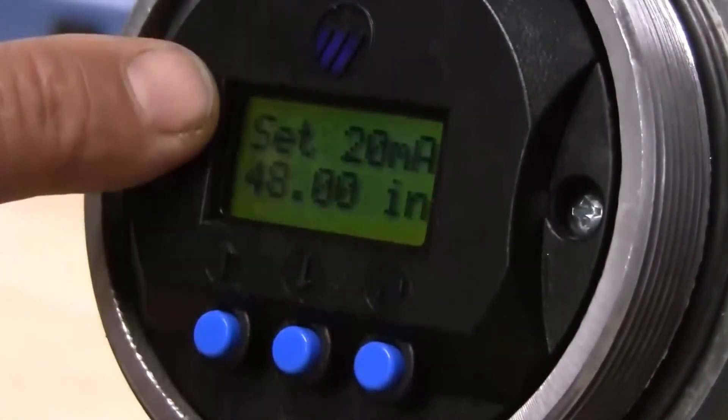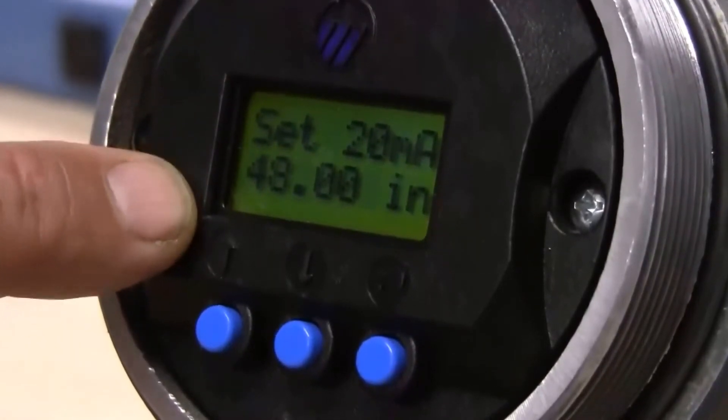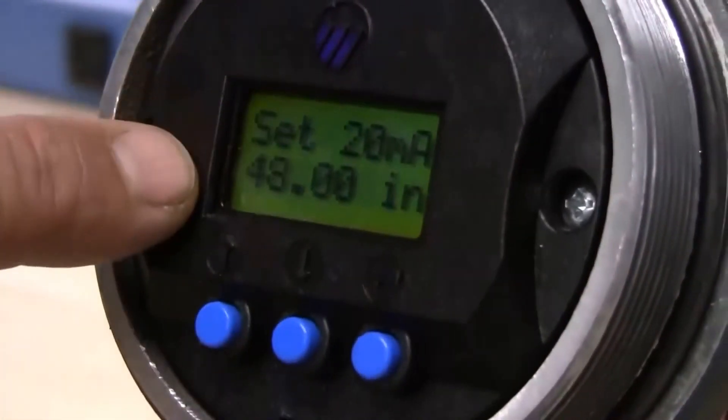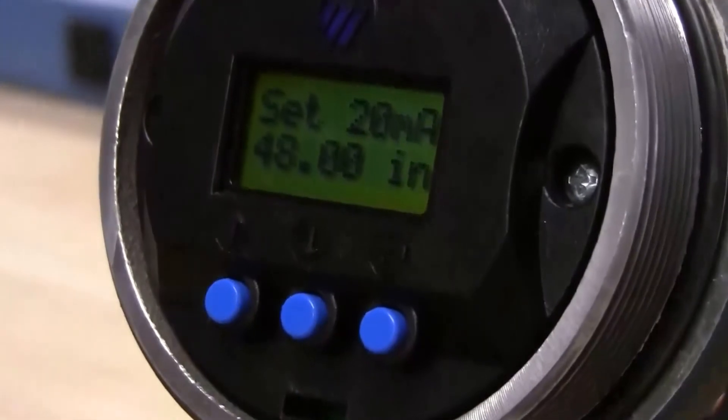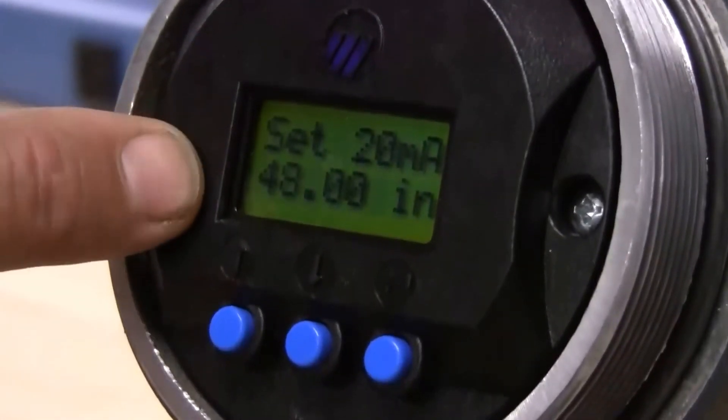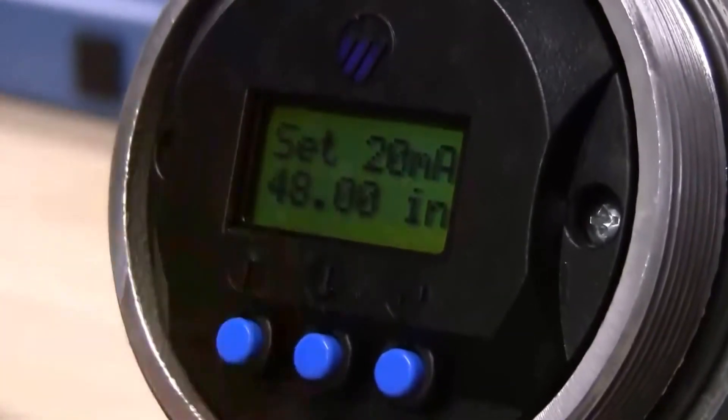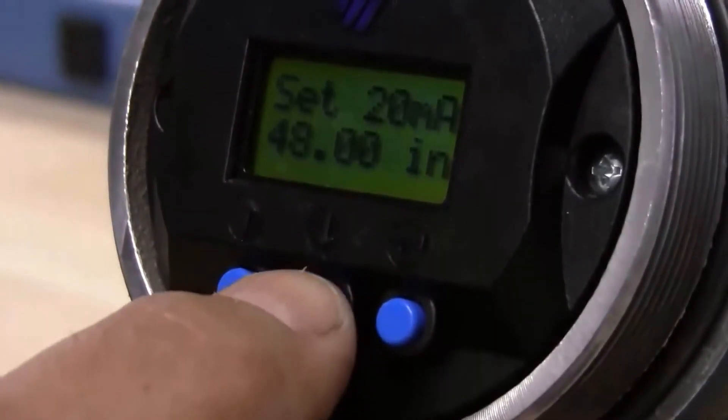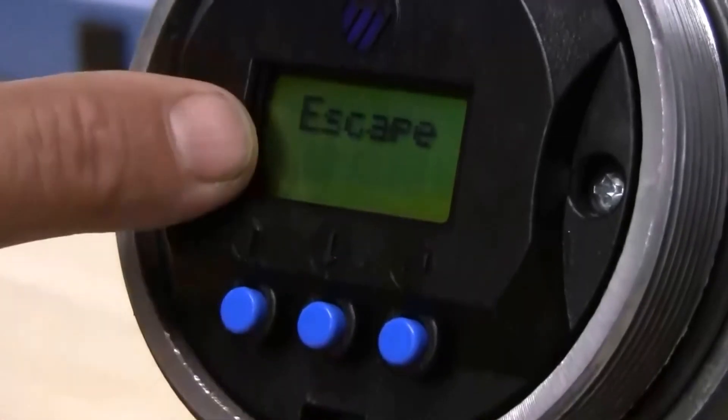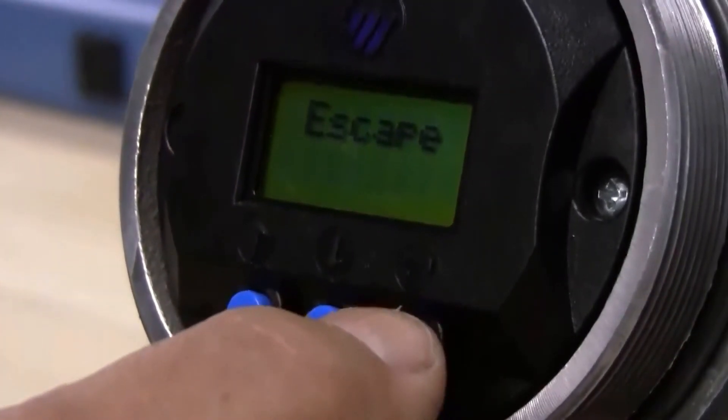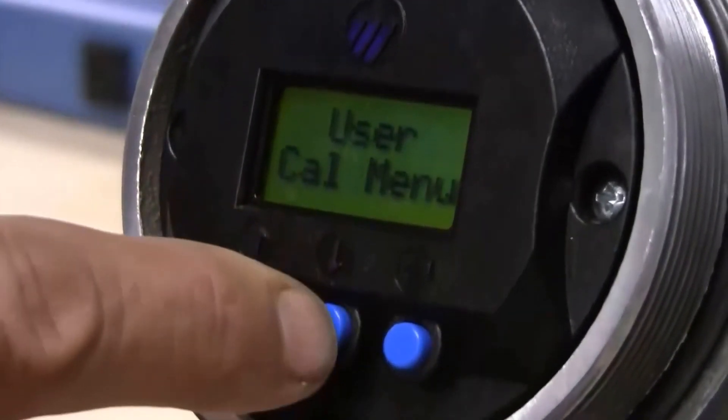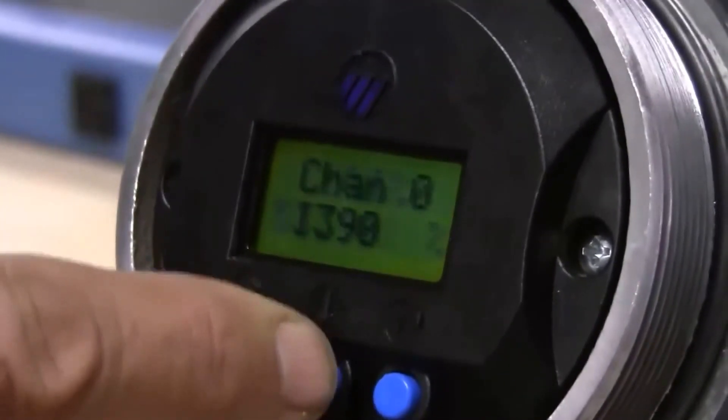And then our set 20, we want 20 milliamps to read out if this was a 48 inch displacer at the top of the displacer. So when the device reads 48 inches, we want it to output 20 milliamps. So we will leave that there. And down arrow and when you see escape, you can just push enter.